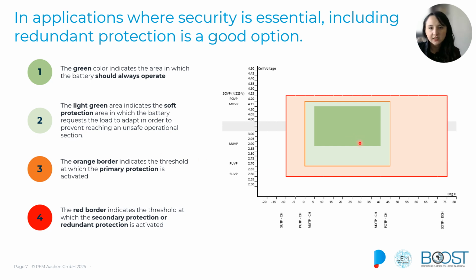Here we have one example that is showing the different layers that a system might have. In the first layer, we can see this dark green color that indicates the area in which the battery should always operate, and this is the area where our battery operates safely. Then we have another layer where the boundaries are a little bit wider, and in this case these are the soft protections. This is an area in which the battery continues operating but already requests to adapt the load, for instance, or to monitor and to send warnings to the system to prevent the unsafe limits from being reached.